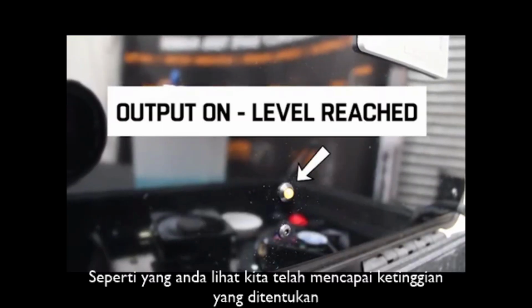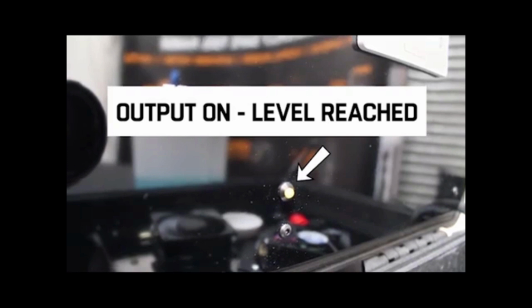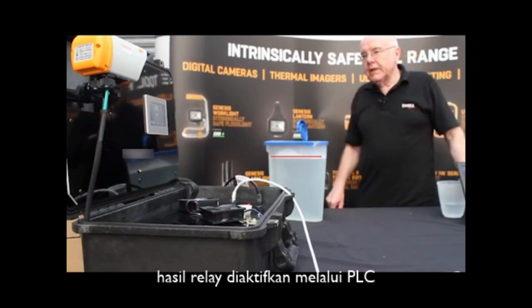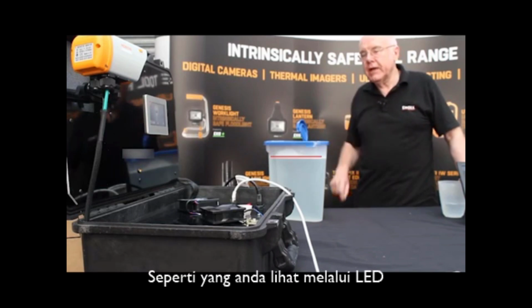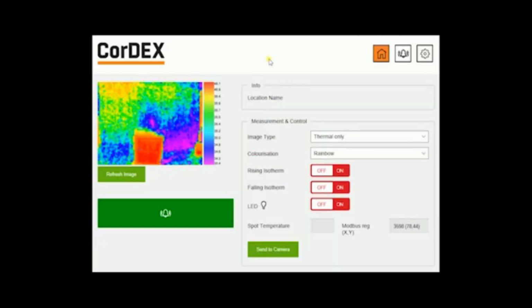And now, as you can see, we've reached the level. The relay output is enabled on the PLC, as you can see by the LED. Here is the thermal image of the container, and if we look at it here, we can see that the level is just a little bit above what we set.